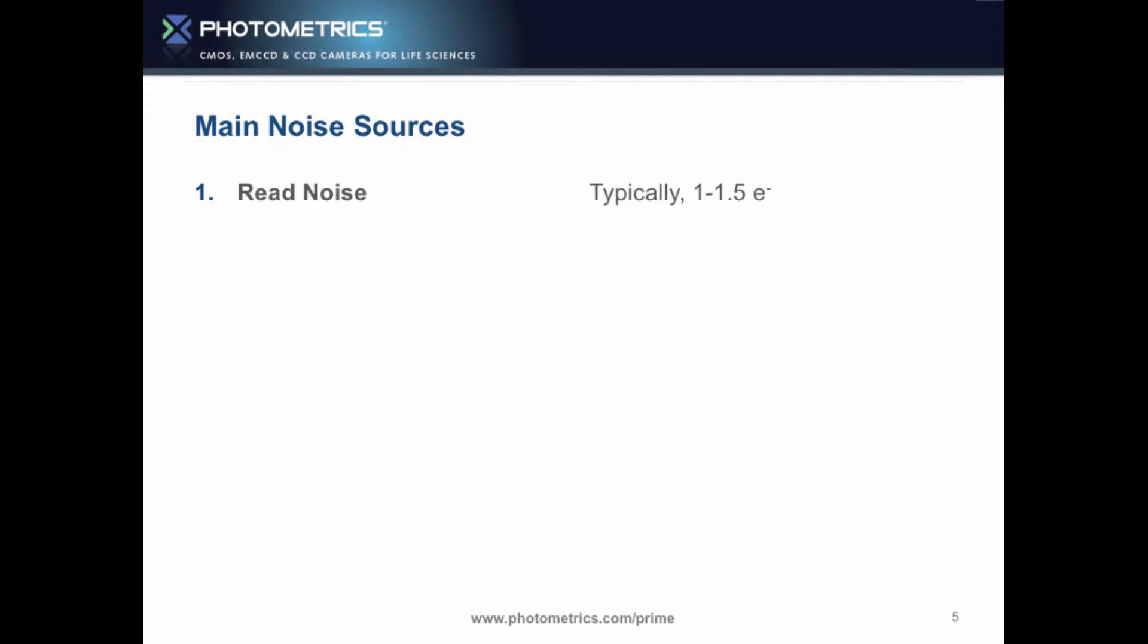So read noise, typically one to one and a half electrons. We actually have some of the lowest statistics for our fastest mode. It's really nice to be market leading on that. Again, on the dark current, this is again a very small number. We have the great cooling. We're 0.06 electrons per pixel per second or less.